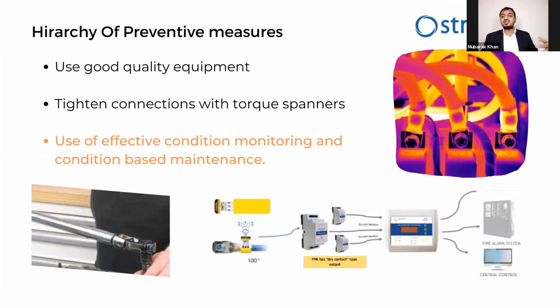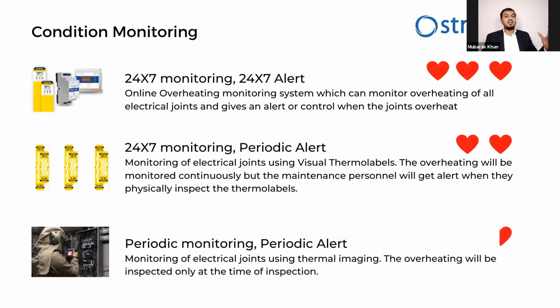Now, the second method is using periodic monitoring using thermography. And one more method is to use an effective condition monitoring and condition-based maintenance system. Okay, we will see each one of them one by one. I'm not going to touch upon the tightening with the torque spanner. It is quite simple. We need to tighten it with the torque spanner. We are going to focus on the condition monitoring and condition-based maintenance. There are 3 ways or maybe more, but I'll touch upon 3 ways in which you can do the condition monitoring of the electrical joints.